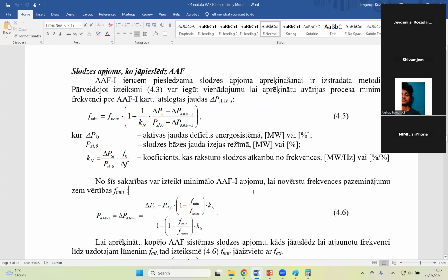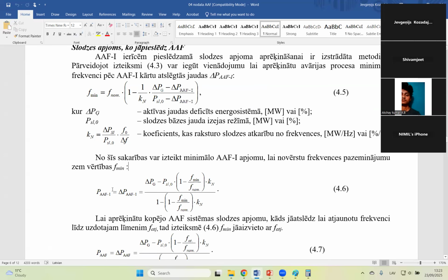Based on this formula, we could calculate how much load power we need to connect to the automation if we want the frequency not to be below this F min value. So how much power must be connected to this automation, so as not to allow the frequency to be lower than this value.